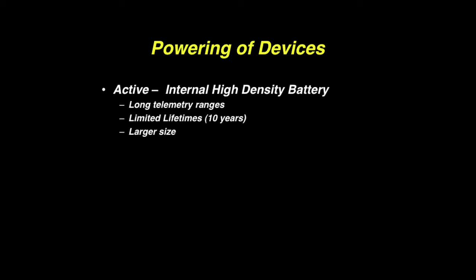For pacemakers, devices use an internal battery. That's called an active method. The advantage of that is that you have a power source that's available inside the body. You can get telemetry ranges, much like you could from Bluetooth or other kinds of technologies. But because the power source is implanted, it's limited to the length of time that power source will last. At best, 10 years for pacemakers. And you end up having larger size because you have to have the battery storage whose volume is related to how much capacity you will have.